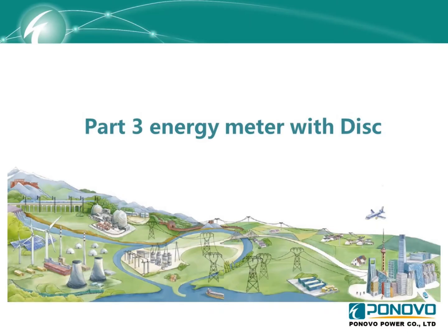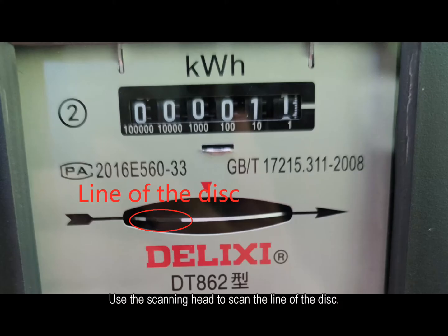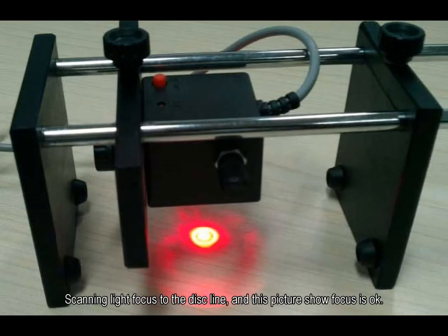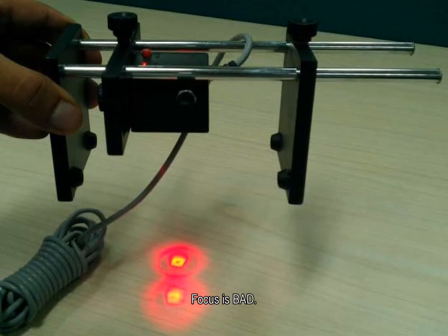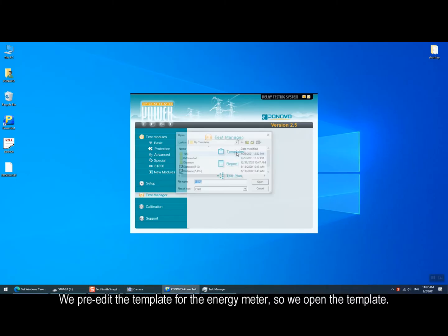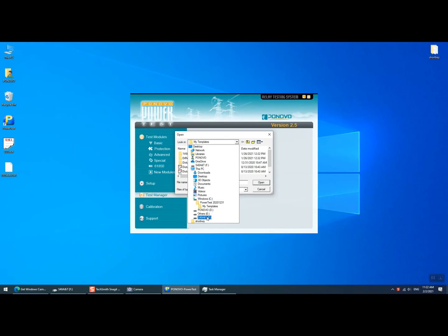And in part 3 we will show how to test the mechanical energy meter with disk. When testing this kind of energy meter the energy meter must be installed vertically. Use the scanning head to scan the line of the disk. When the scanning light focus to the disk line this picture shows focus is ok. If the focus light is like this photo, it means the focus is bad. And we need to make sure the focus light is good before the testing.